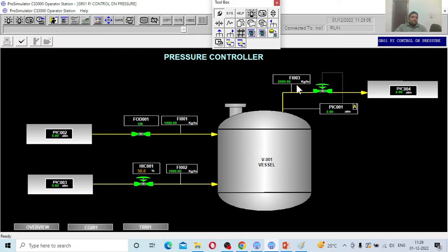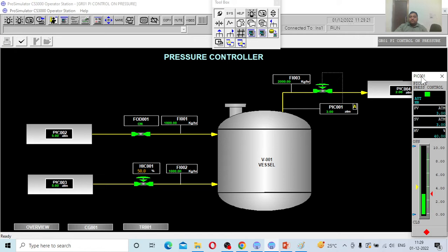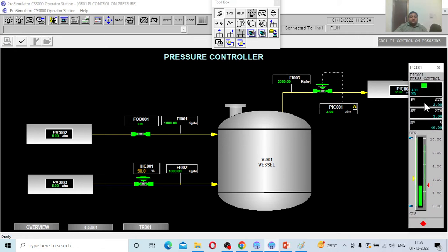At steady state, the flow outlet is 2000 kg per hour, which is the summation of FI 001 and FI 002. If I click the controller, the pop-up window shows that the present process value — the pressure inside the vessel — is 3 atmospheres. I also want to maintain 3 atmospheres in this vessel. To maintain this pressure, the valve has to be open 40 percent, because the exit pressure is 2 atmospheres.